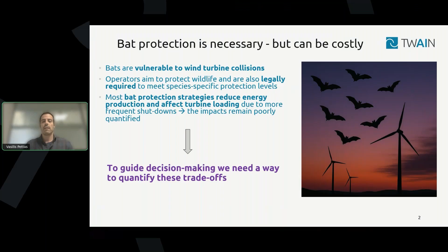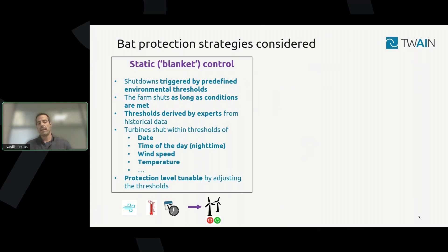First is static or blanket control. In this case, the shutdown of the turbines is triggered by predefined environmental thresholds. When these thresholds are met, the wind turbines shut down. These thresholds are derived in the pre-construction phase by experts, who, based on the flora and fauna of the region, identify variables such as wind speed, temperature, humidity, precipitation, dates, and time of day that define these thresholds, which are tunable to different protection levels, so we can have protection levels like 90%, 99%, 100%, etc.